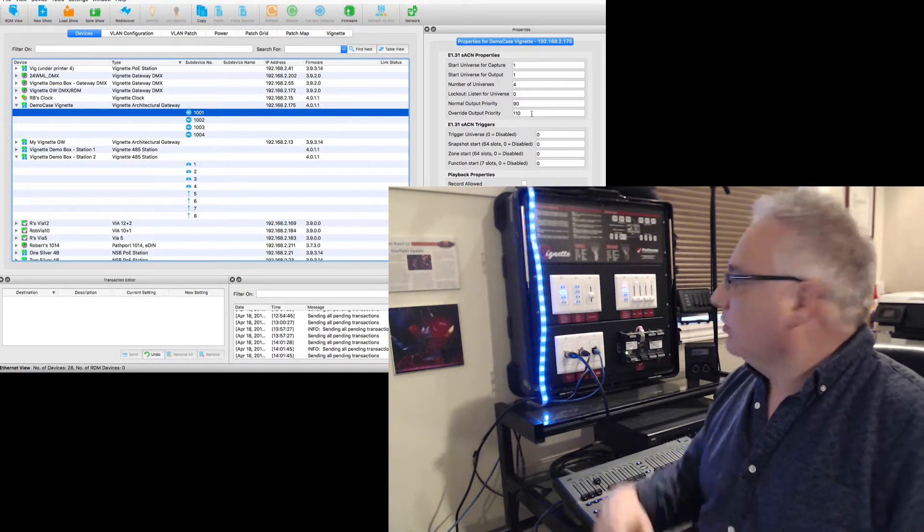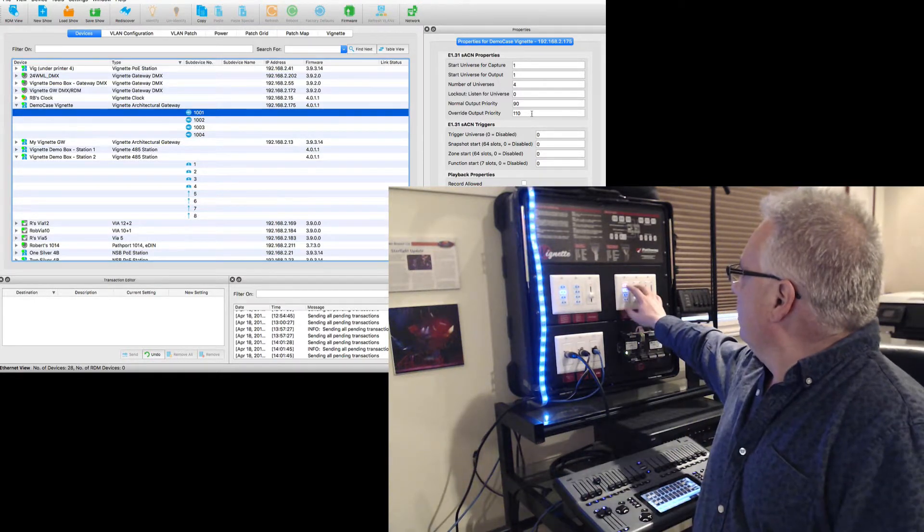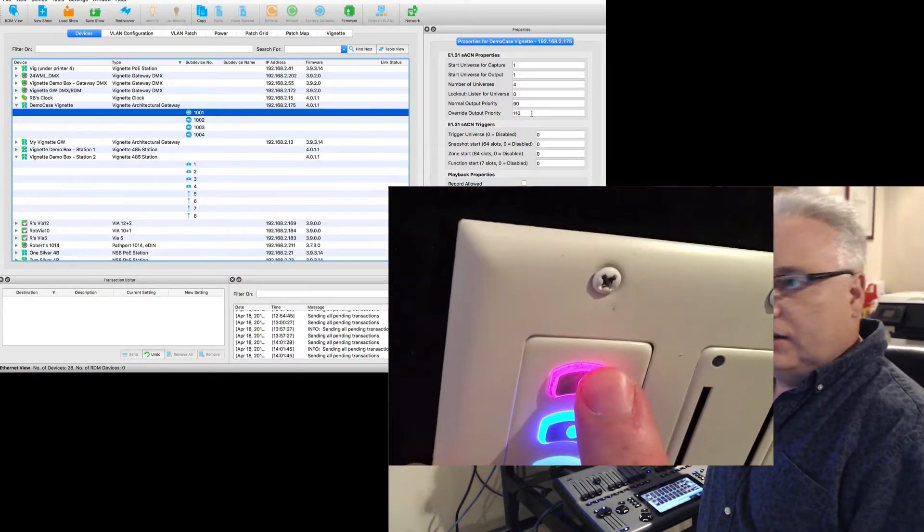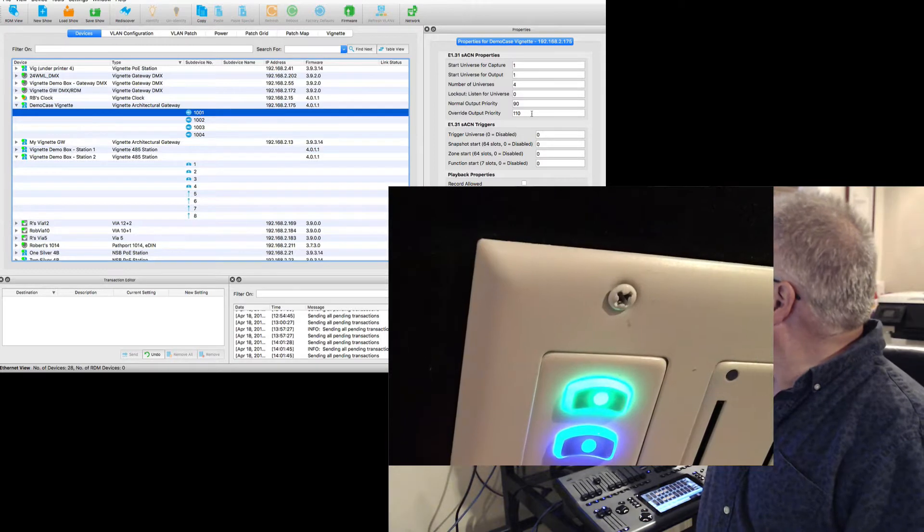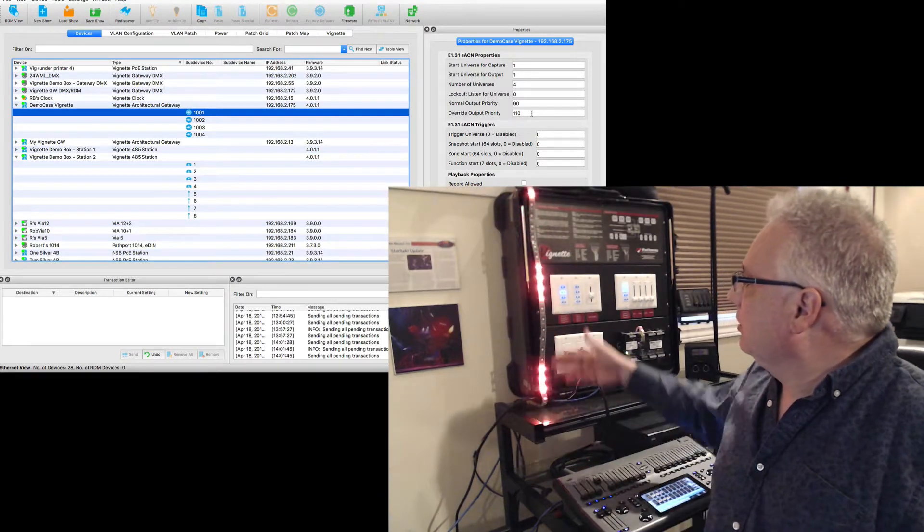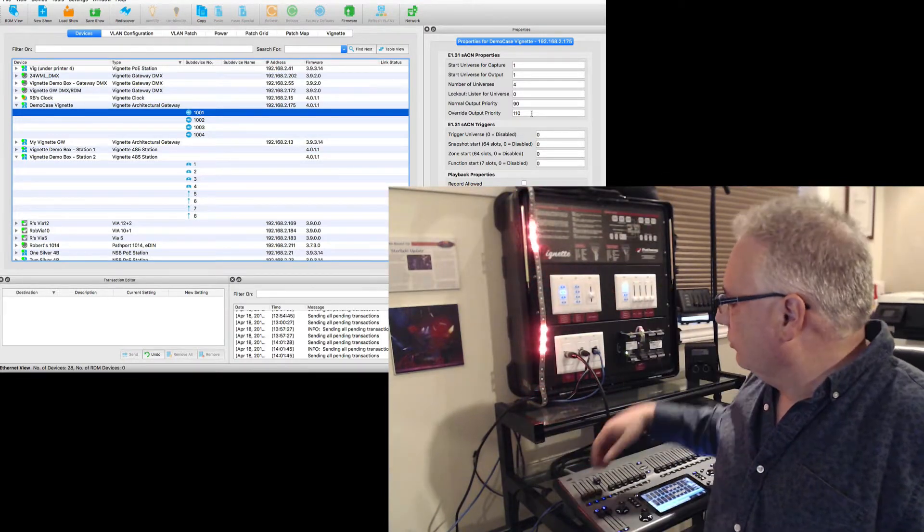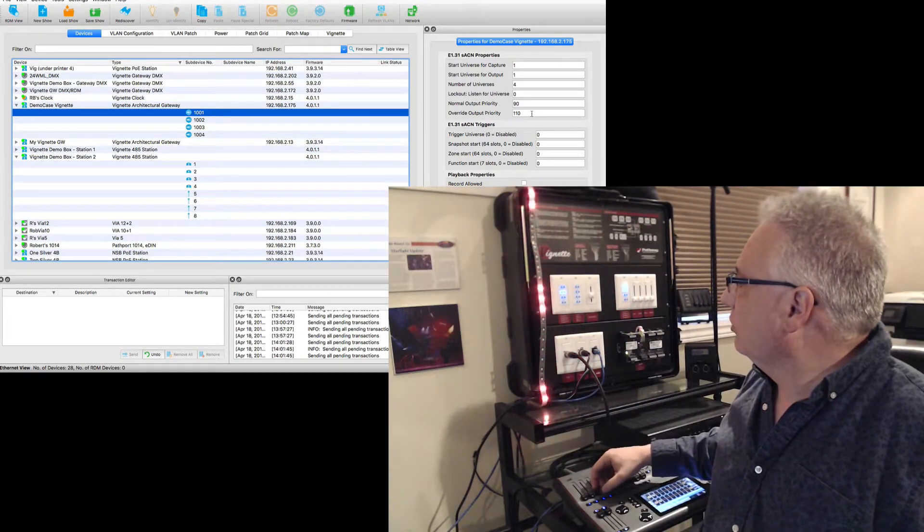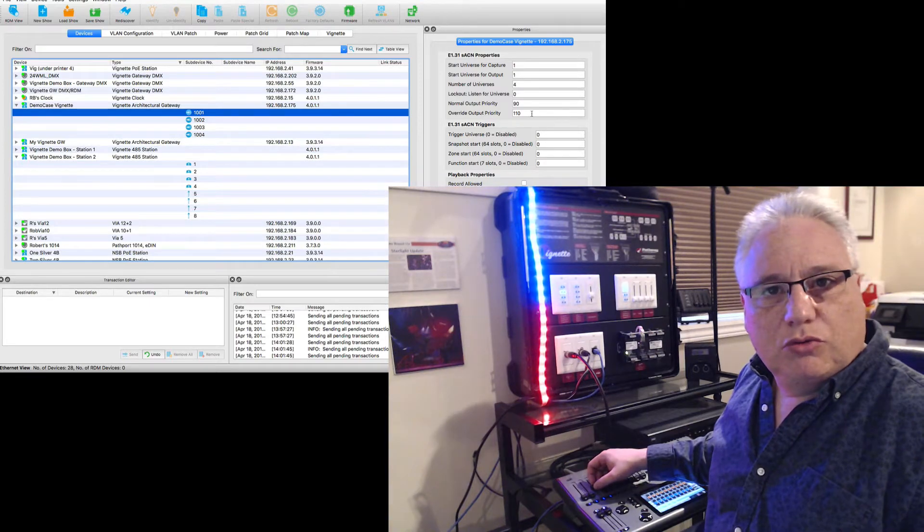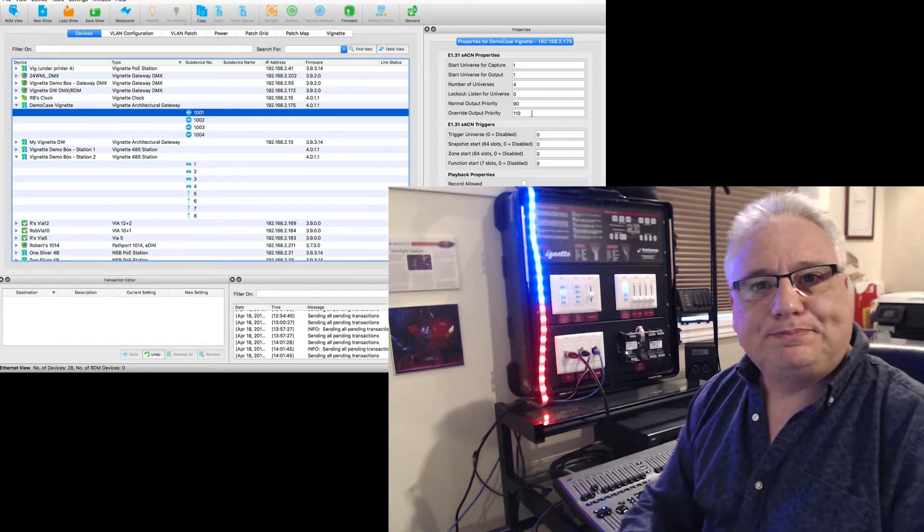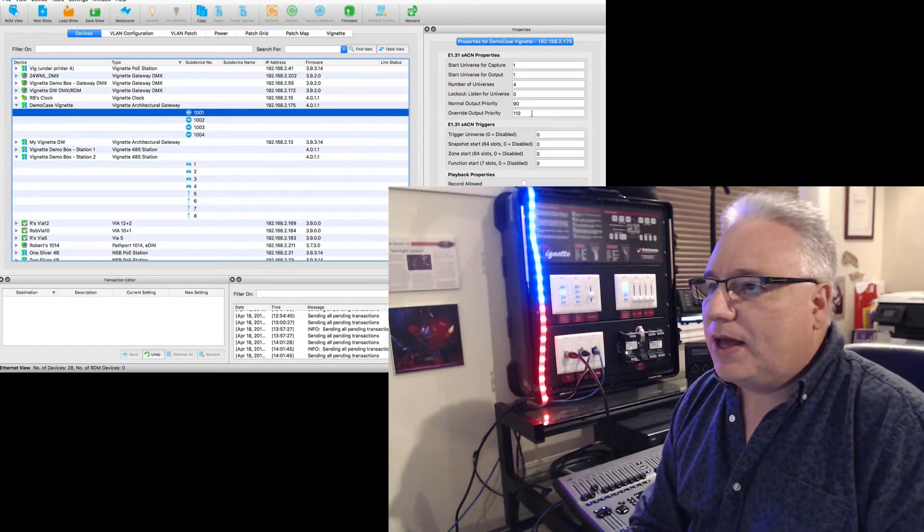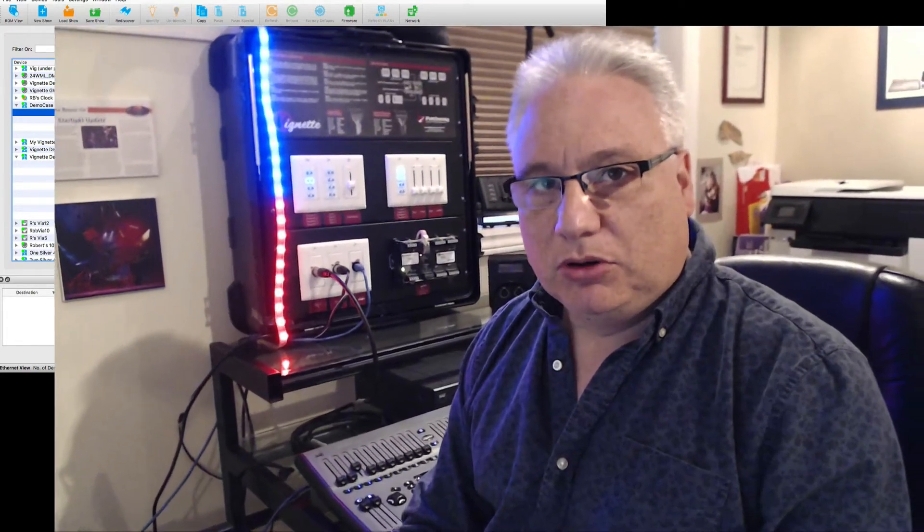And now break is over, emergency is over, whatever it is. We can relinquish control back to the lighting console just by pressing this button. And immediately now you see that the lighting console has control over the system again. So that is normal versus override output priority in your Vignette snapshot and zone controller.